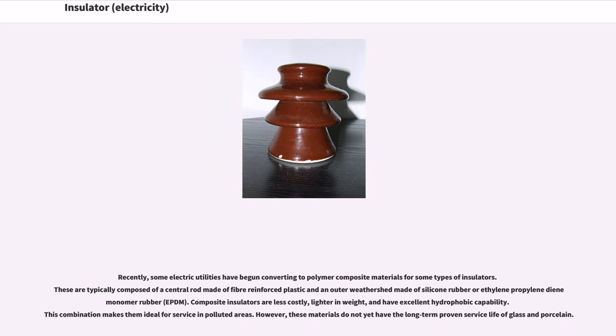Recently, some electric utilities have begun converting to polymer composite materials for some types of insulators. These are typically composed of a central rod made of fiber-reinforced plastic and an outer weathershed made of silicone rubber or ethylene propylene diene monomer rubber. Composite insulators are less costly, lighter in weight, and have excellent hydrophobic capability. This combination makes them ideal for service in polluted areas. However, these materials do not yet have the long-term proven service life of glass and porcelain.